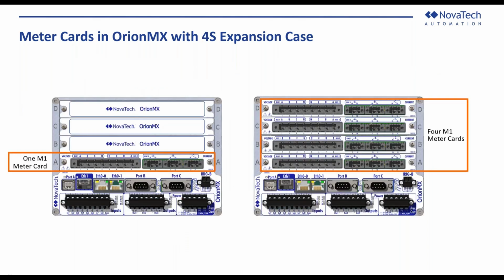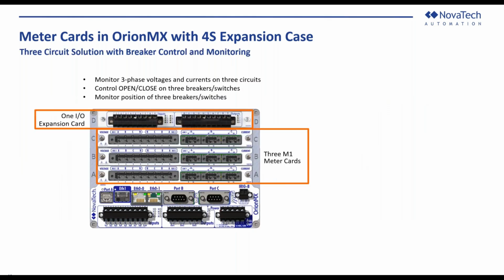We have a larger case in the 4S expansion case, and you can put between 1 and 4 M1 meter cards in the 4S case. This shows a combination of 3 meter cards and 1 IO expansion card. This again would measure three-phase voltages and currents on 3 circuits. It also could control open close on 3 breakers or switches, or monitor the positions of 3 breakers and switches. And one reason we put this in here is that this is going to be one of the first applications we talk about, how to add this type of automation to a legacy substation.